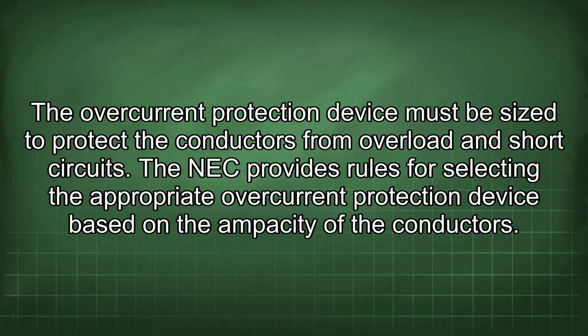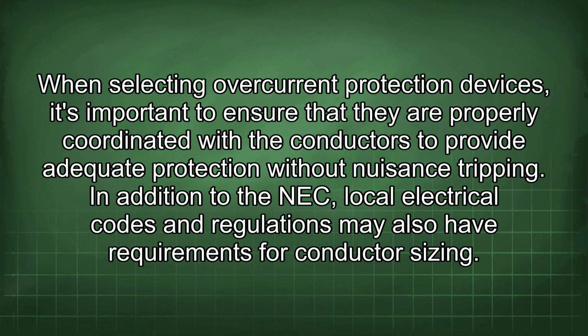The overcurrent protection devices, such as circuit breakers and fuses, also play a role in conductor sizing. The overcurrent protection device must be sized to protect the conductors from overload and short circuits. The NEC provides rules for selecting the appropriate overcurrent protection device based on the ampacity of the conductors. When selecting overcurrent protection devices, it's important to ensure that they are properly coordinated with the conductors to provide adequate protection without nuisance tripping.